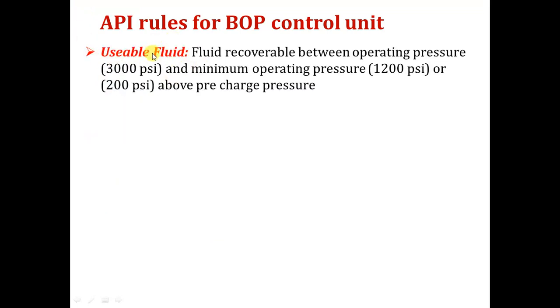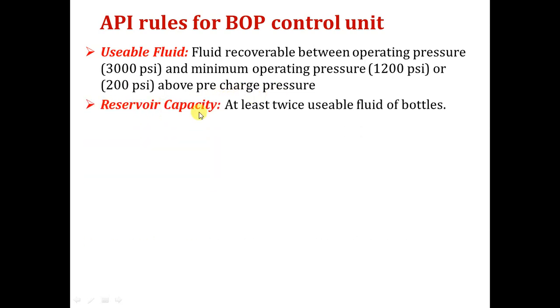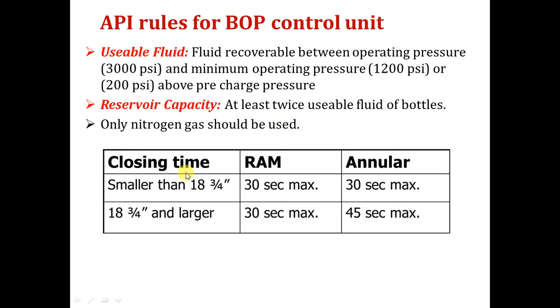The minimum number of accumulator cylinders is four. Per API, the unit can operate with up to one quarter of cylinders without pre-charge (e.g., if 16 cylinders, 4 may be unusable), but if more than a quarter are unusable the unit is not accepted. The reservoir capacity must be at least twice the usable fluid volume of the bottles. Closing time for all rams must not exceed 30 seconds. For the annular BOP: if smaller than 18¾ inches, closing time is less than 30 seconds; if larger, no more than 45 seconds.